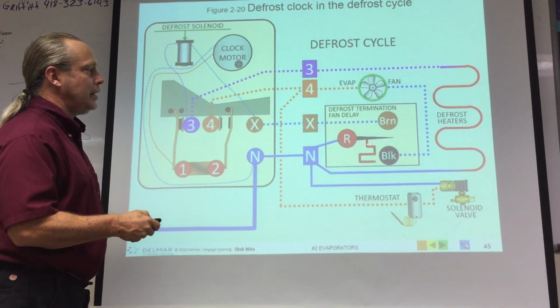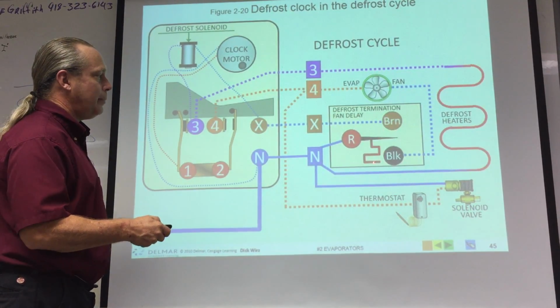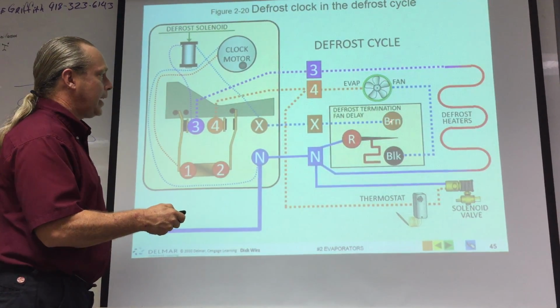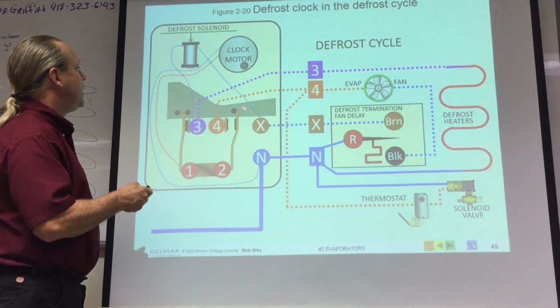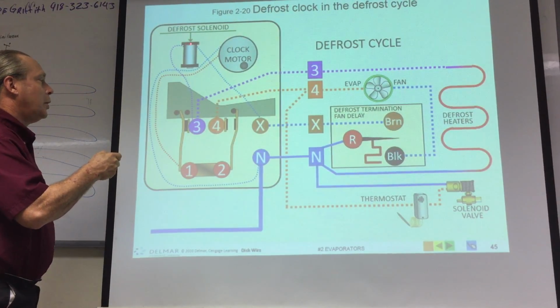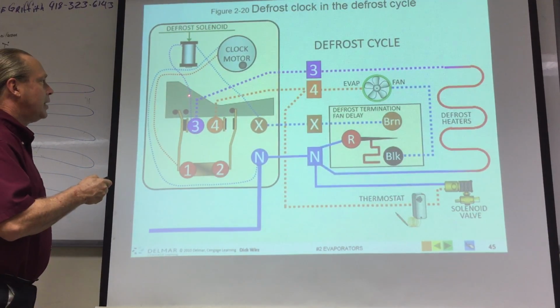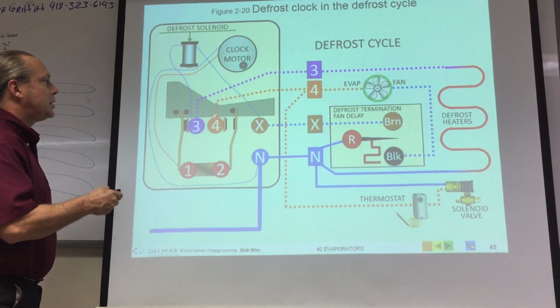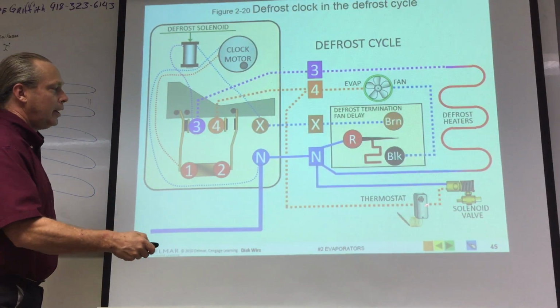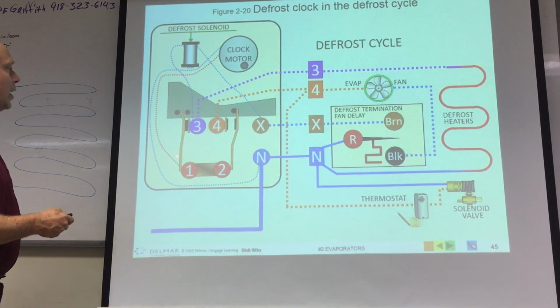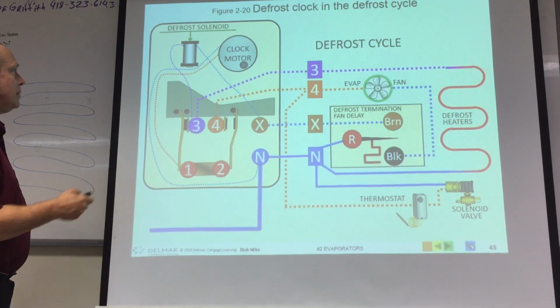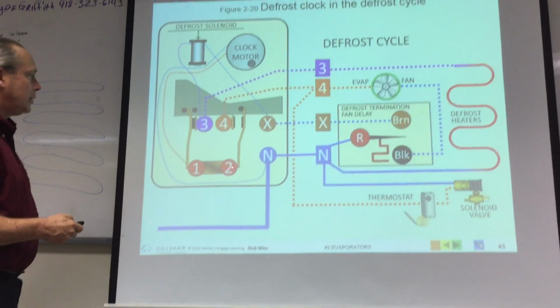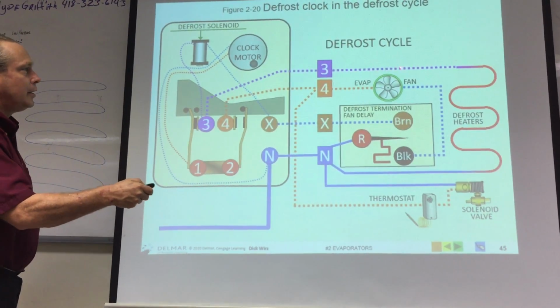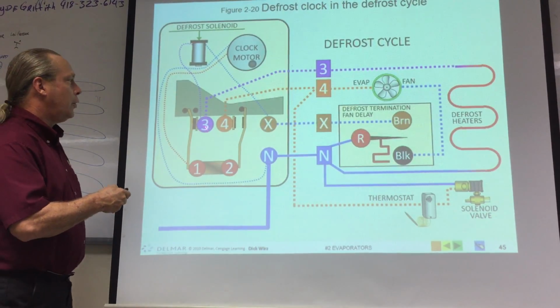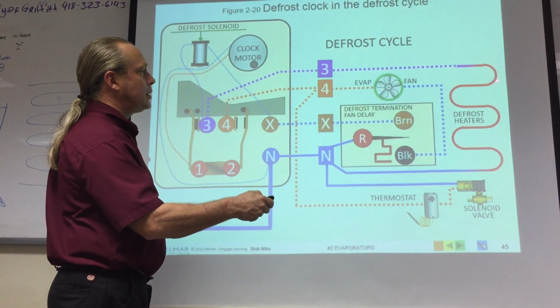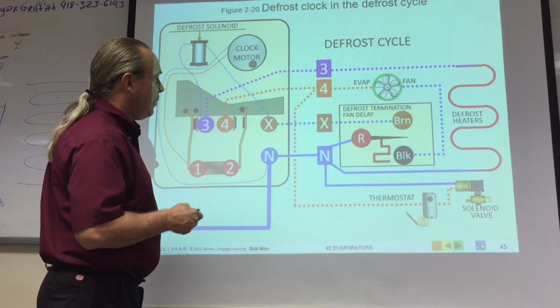If this should continue to expand, this little bimetal element, and connect with brown, that's going to hit X, which is going to energize the solenoid. And the solenoid is going to push this over, reestablishing the connection to the evaporator and the thermostat. As of right now, it's got it shut off. 3, 2. Yeah, if we go from 1 through 3, we'll go to the defrost heater and back to neutral.